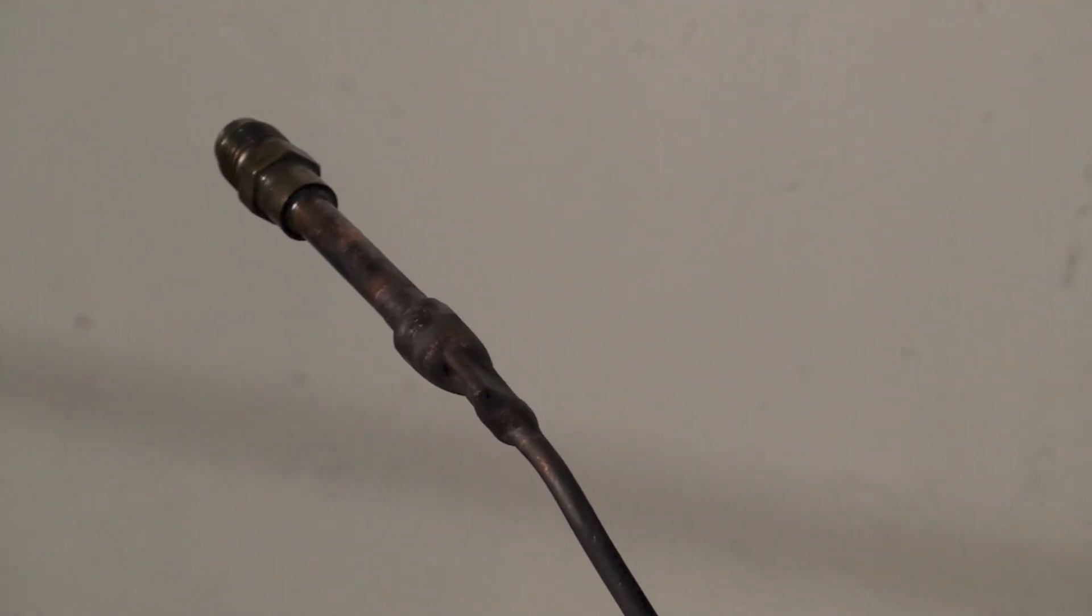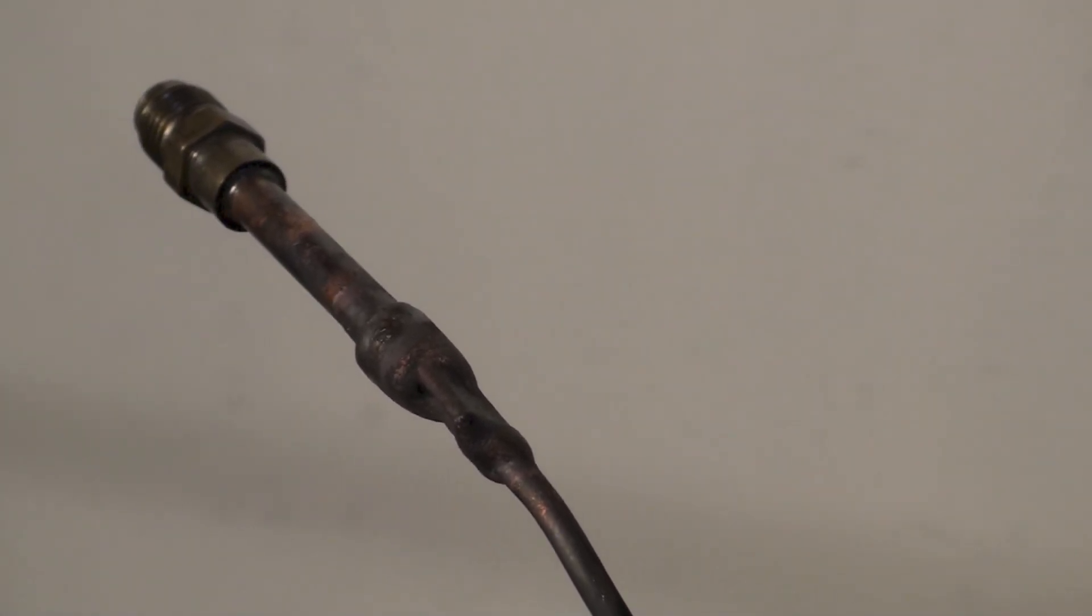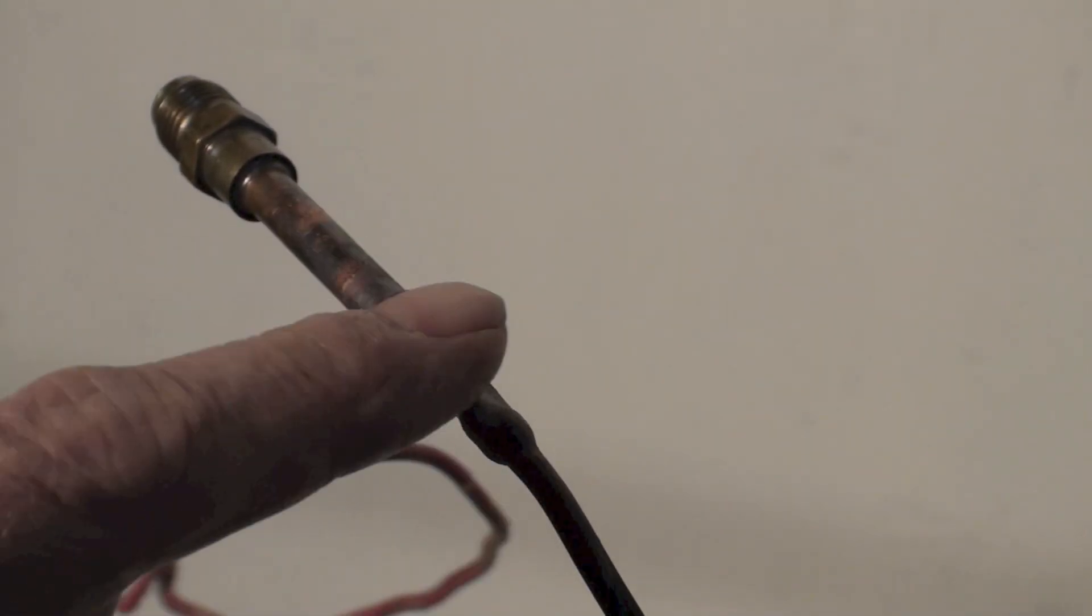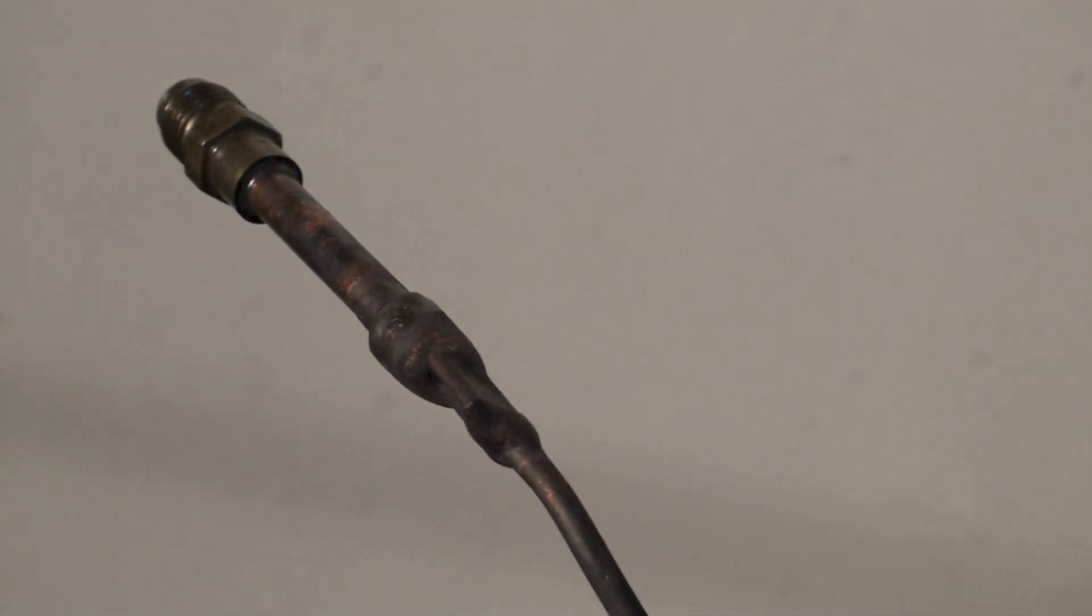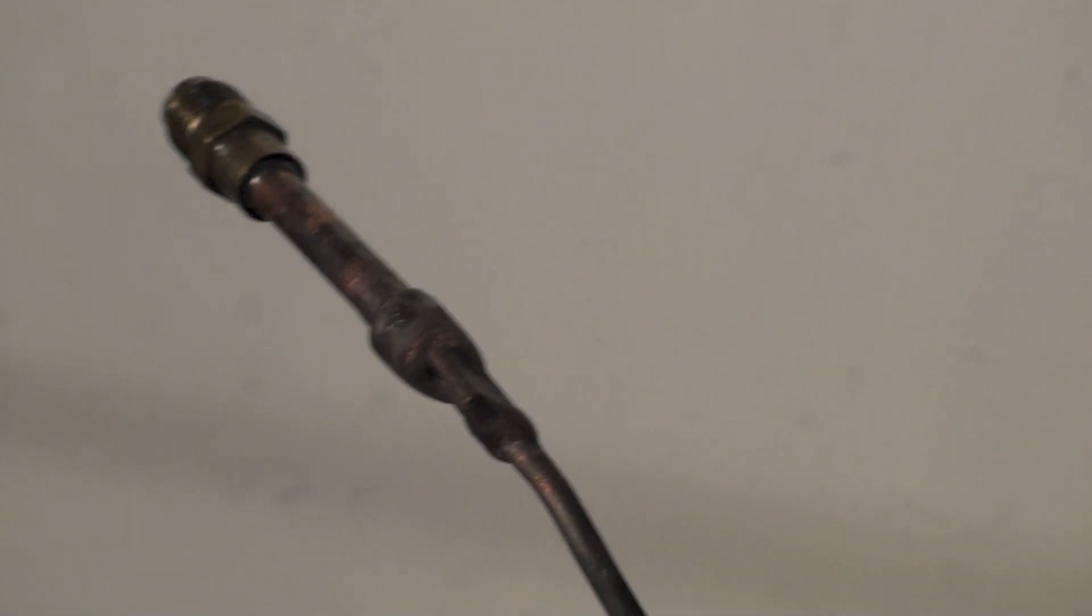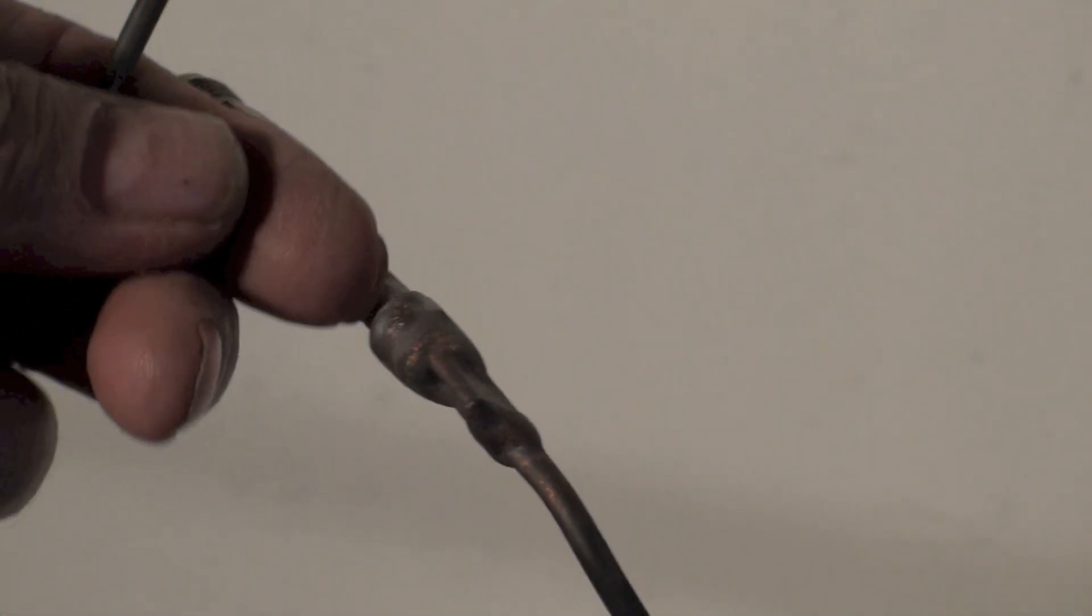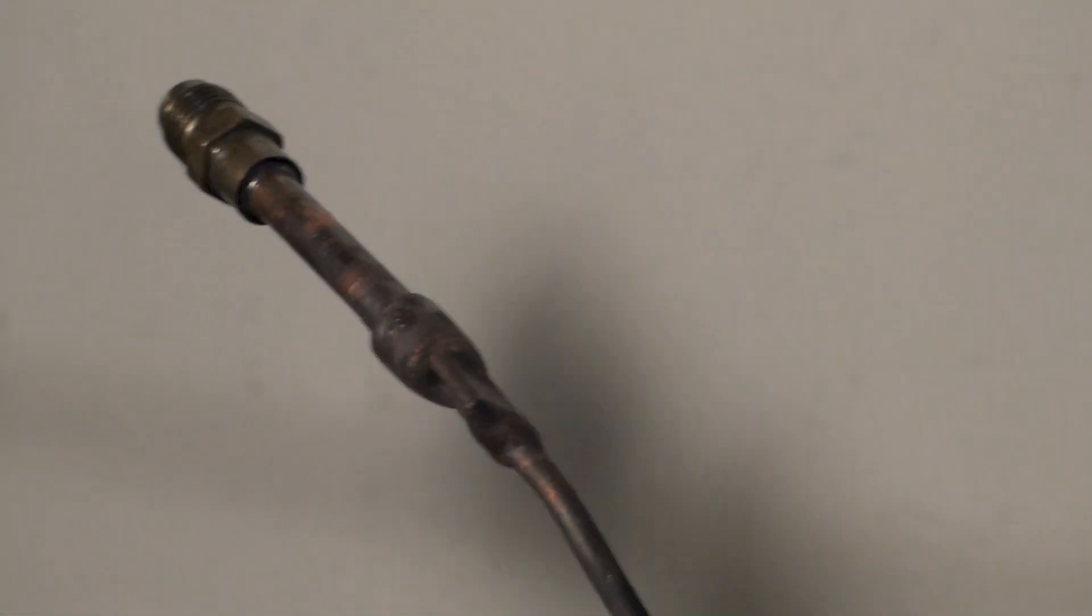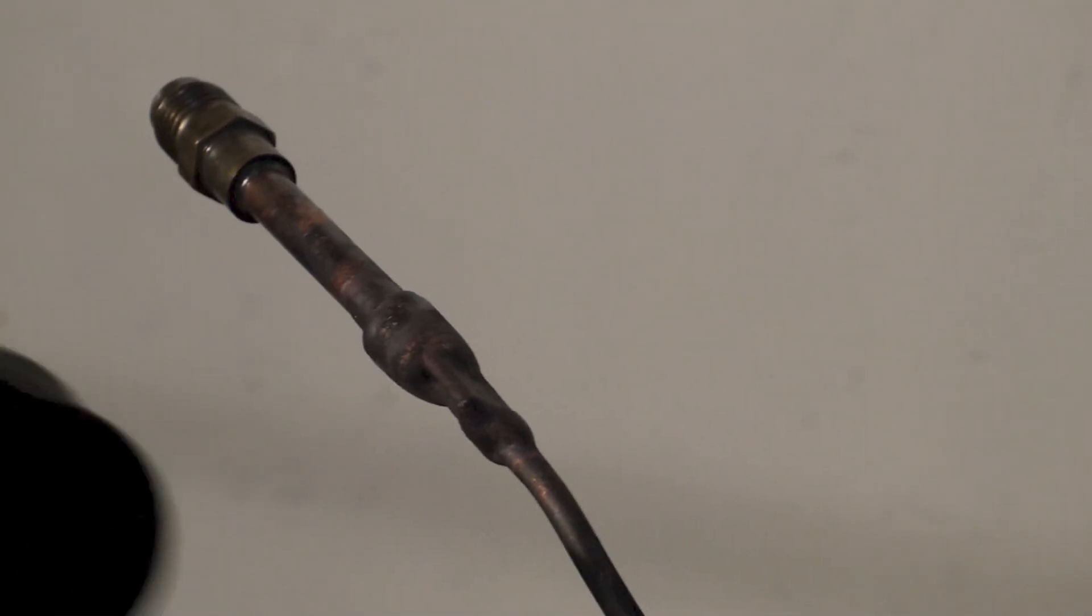Where the cap tube goes in here, they usually take the larger tube and squish it down and then just braze in the capillary tube. Well, I've taken advantage of this by using just a short piece of this tubing and putting this fitting in there because it fit pretty well. Now I'm gonna be taking that off.